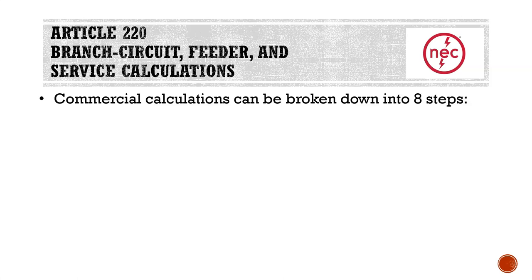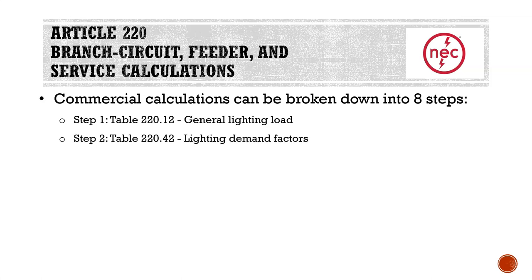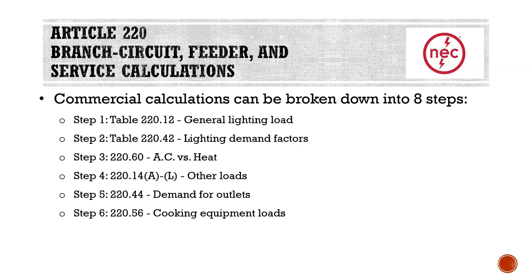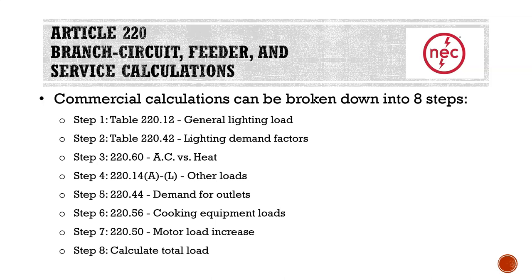Commercial calculations can be broken down into eight steps, as opposed to nine steps for our dwelling calculations. Step one is going to be the same as the dwelling calculation — Table 220.12 for our general lighting load. Then we're going to skip a step we'd normally do for a dwelling calculation and go straight to our lighting demand factors. Then we're going to compare our AC versus our heat again. We have a new step with 220.14 A through L for other loads, then 220.44 for receptacle demand, 220.56 for cooking equipment loads, 220.50 for motor load increase, and finally step eight: calculate total load.